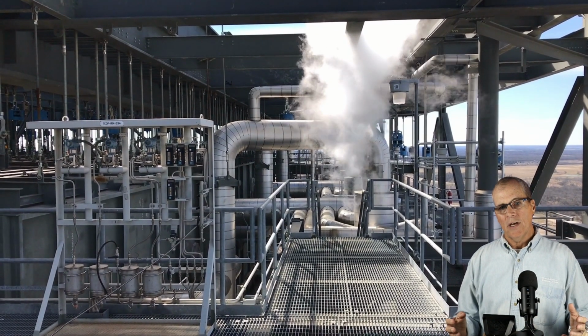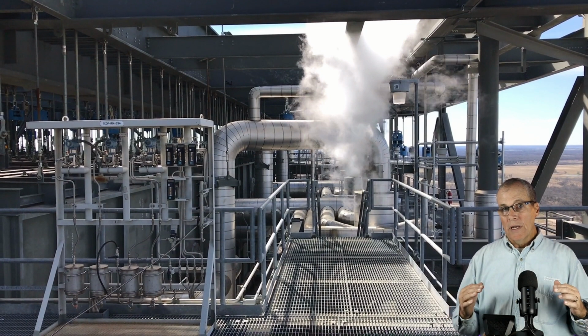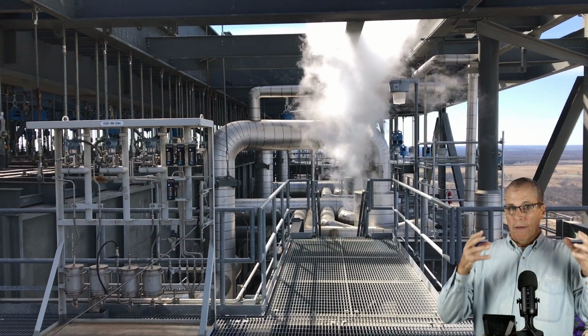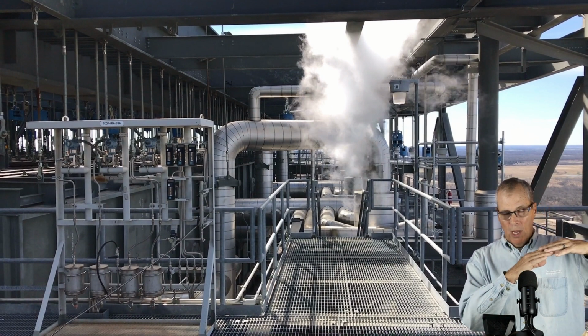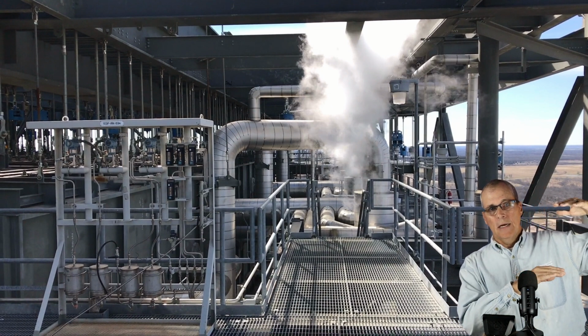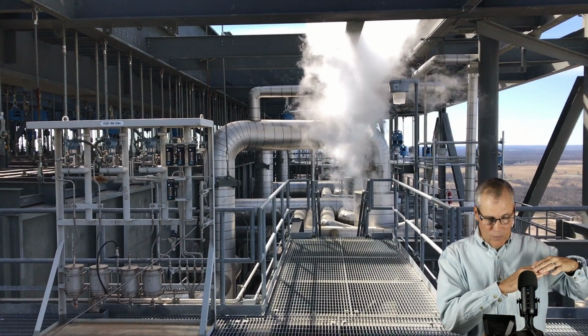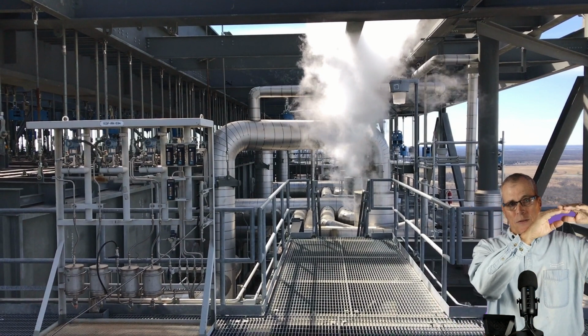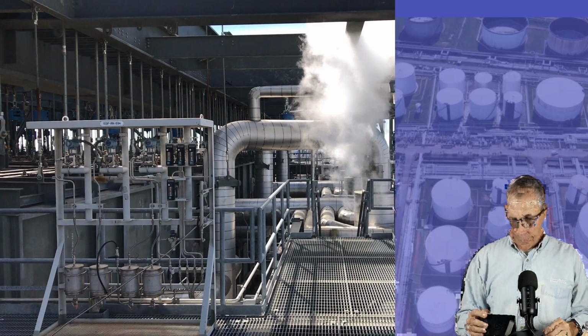That just gives you the idea that boilers are basically built within the building. They hang from the inside of the building. They're not supported by the bottom, and that's because as big as they are, when they heat up, they stretch. And we don't want them to run out of room, so we build all that design in, and they stretch from the top down.